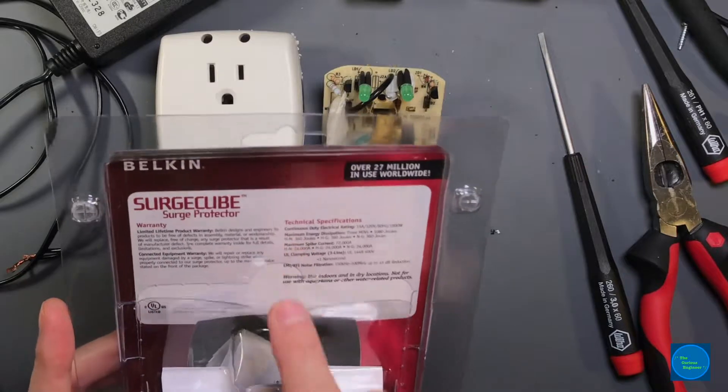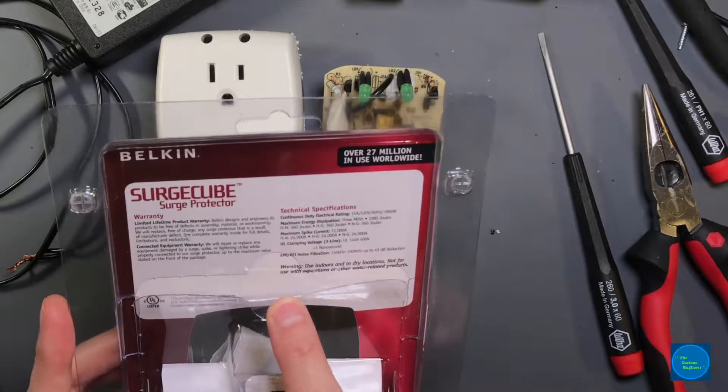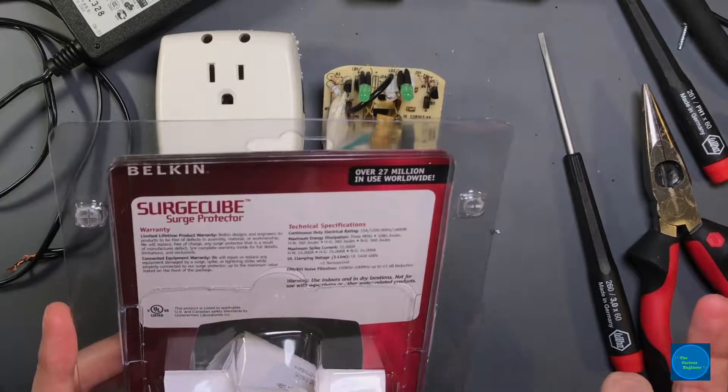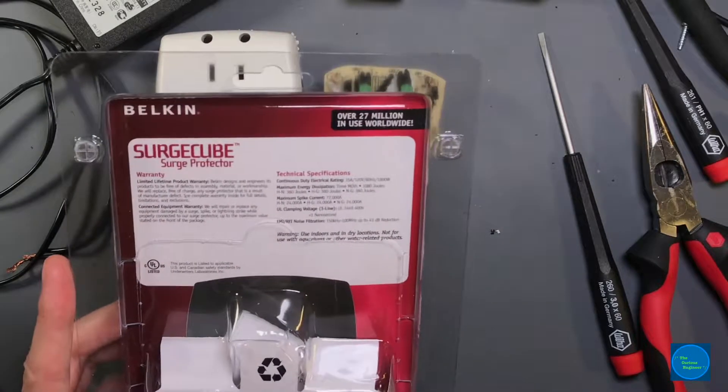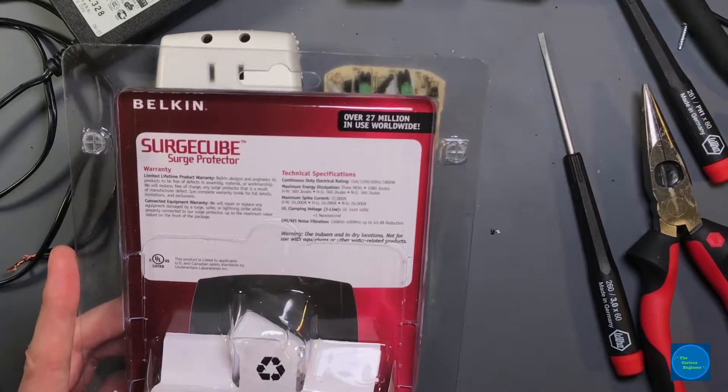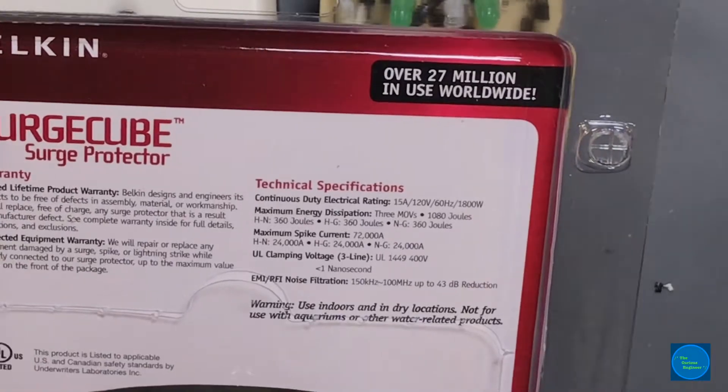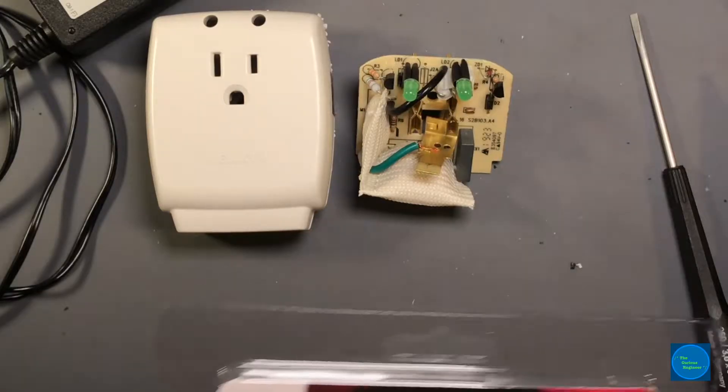The EMI RFI noise filtration is 150 kilohertz to 100 megahertz at up to 43 dB reduction. We'll get to that in a moment as well. These are the ratings that typically you'll see on surge suppression devices. That's what it is.